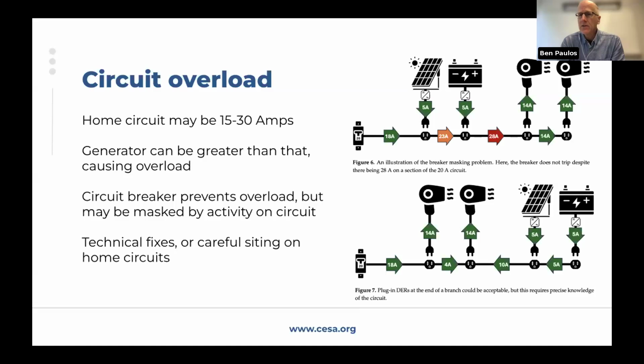In the top case, if you plug in your solar generator and your battery upstream from the two hair dryers, that can do what's called breaker masking, because in this case, the solar panels and the battery are putting out 5 amps each, so that 10 amps makes the breaker think that there's only 18 amps on the circuit, when in fact there's 28 amps on it at the end of the circuit. So that part where the red arrow is can get hot, and that's where you could start a fire in your house, and the circuit breaker would not realize that.